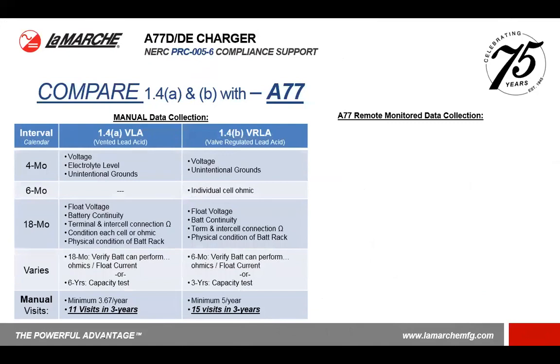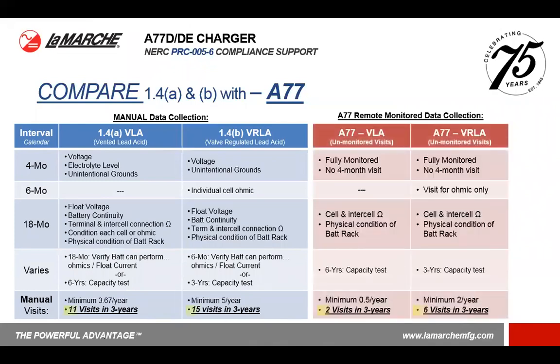So let's compare the overall table for manually collected data versus A77 remote monitor data collection. This table you've seen before. It's the same one that resulted in 11 visits in 3 years for a VLA and 15 visits in 3 years for a valve-regulated lead-acid battery. Well, the A77, on a vented lead-acid battery, could reduce that to 2 visits in 3 years. And that's because the 4-month interval is fully monitored.